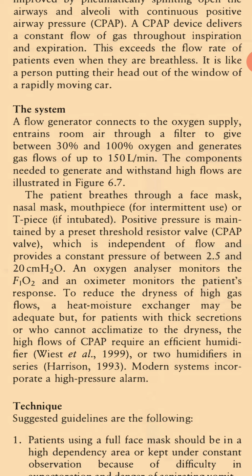The patient breathes through a face mask, nasal mask, mouthpiece for intermittent use, or T-piece if intubated. Positive pressure is maintained by a preset threshold resistor valve (CPAP valve), which is independent of flow and provides a constant pressure of between 2.5 and 20 cm H2O. An oxygen analyzer monitors the FiO2 and an oximeter monitors the patient's response.